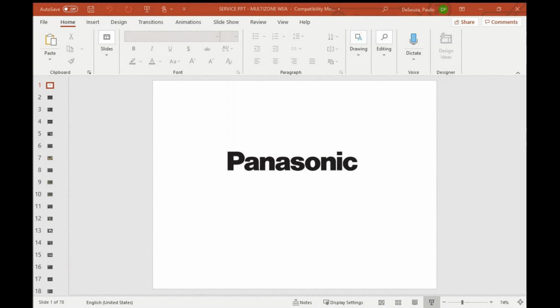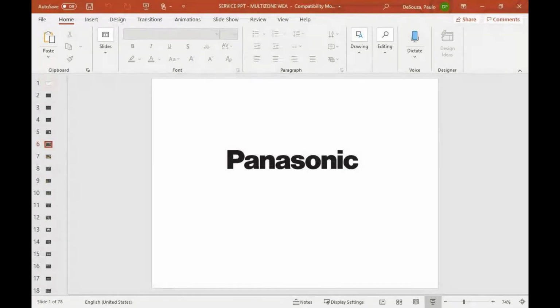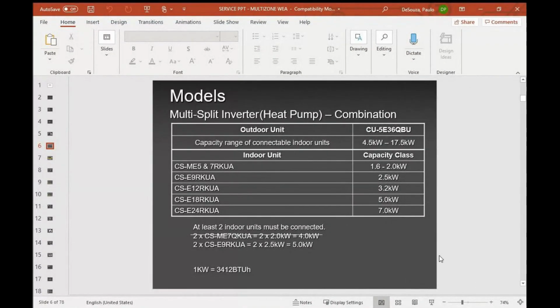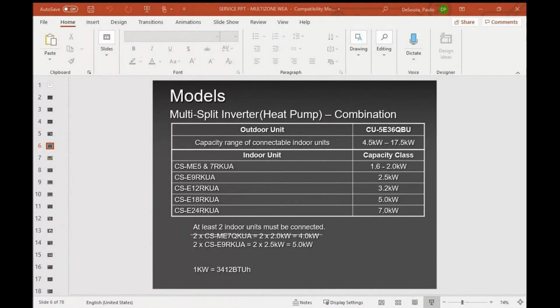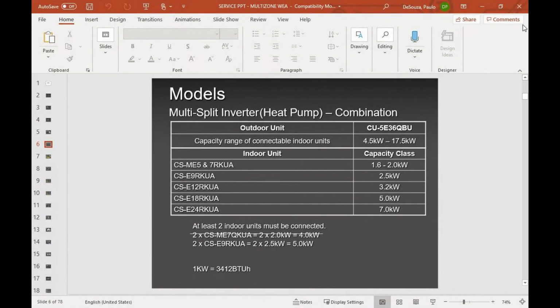In the next few seconds, you will see how much a kilowatt is. When we do the conversion, 1 kilowatt is 3,412 BTUs. All you do is multiply by this number to convert into BTUs. Our lowest capacity, as far as our multi-zone is concerned, whether it's wall mounted, cassette or ducted, is 5,000 BTUs. Then comes the 7, then the 9, 12, 18, and 24. So when we say a minimum of 2 indoor heads, keep in mind you have to respect the minimum and maximum capacity.